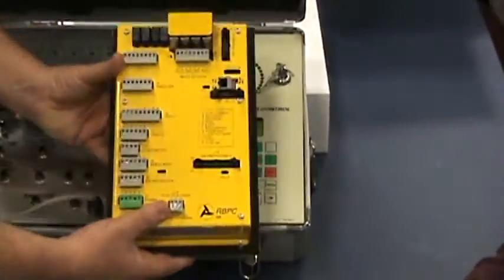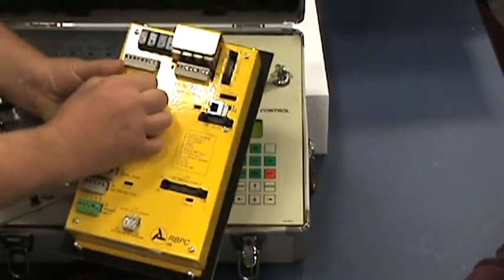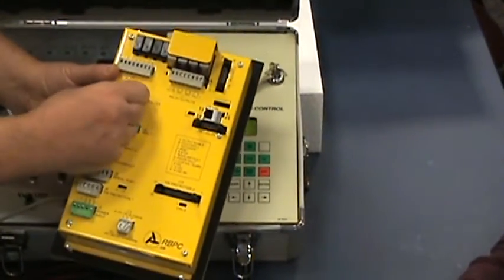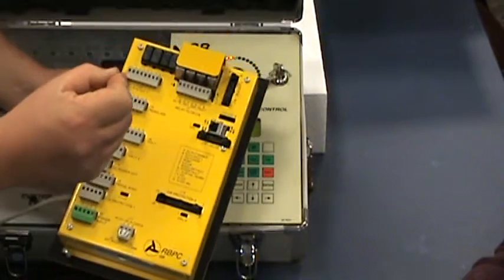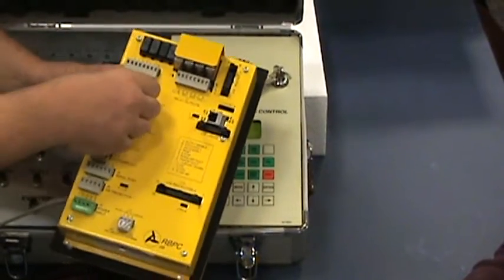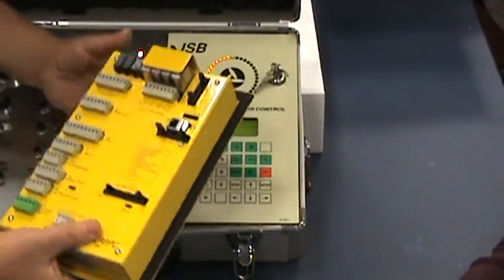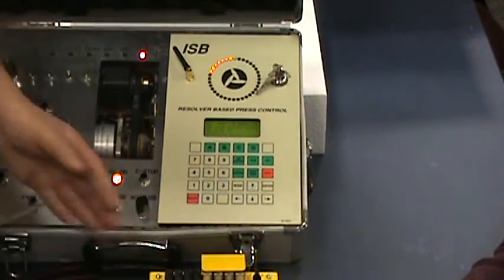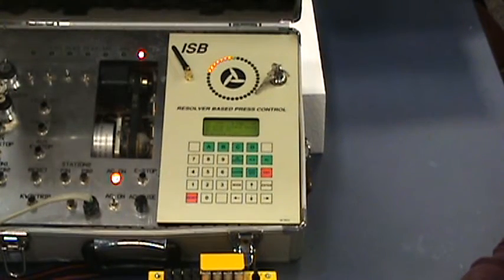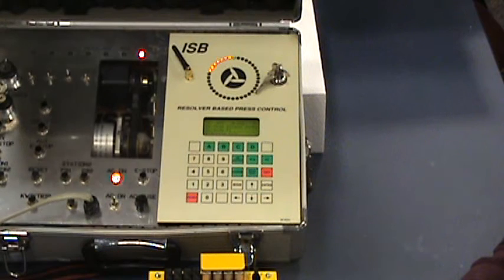The back side, every connection is made via Phoenix terminal blocks. These blocks unplug, you hook your wires up, you plug them back in. So that's an important part of your installation. Be neat in the beginning, use like 16 gauge machine tool wire, make sure your wires are not frayed, put them in correctly.